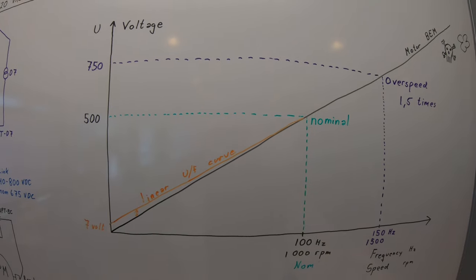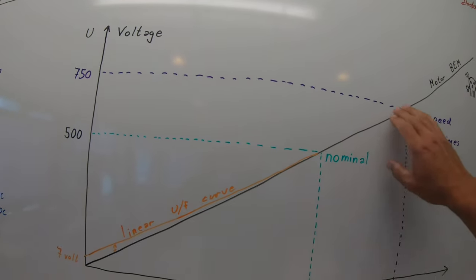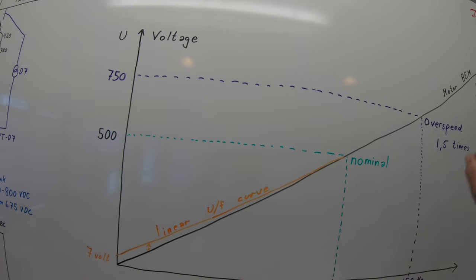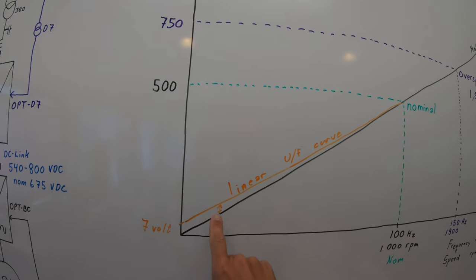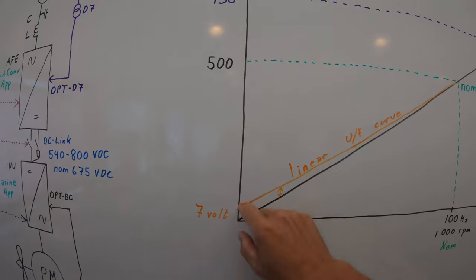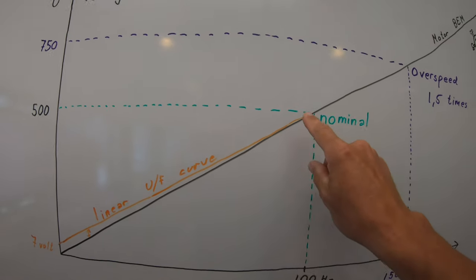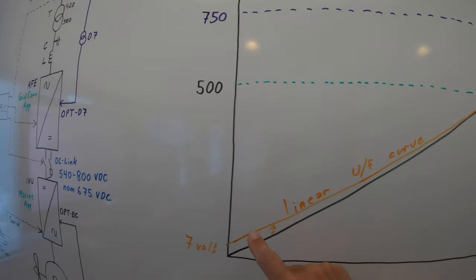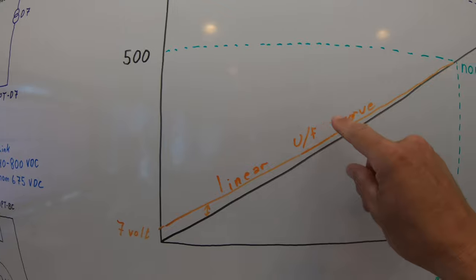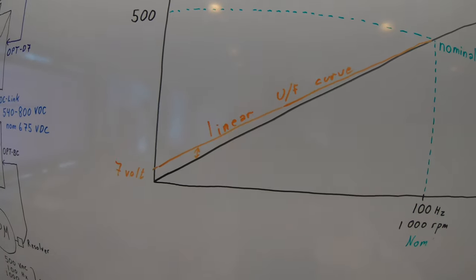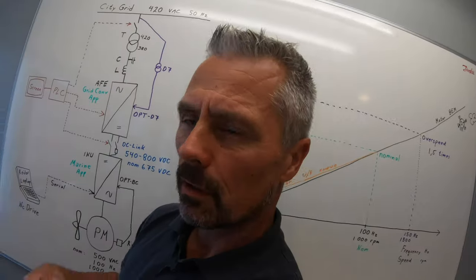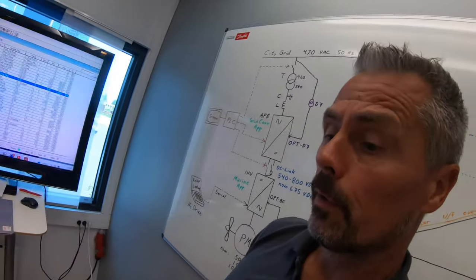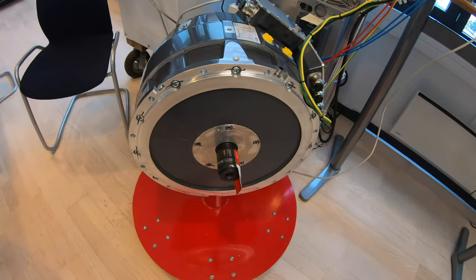How does this look on our back EMF curve? The motor itself, if you spin it, it will produce this back EMF voltage. And this orange color is now our linear UF curve. Here we start at 7 volts which will produce some kind of current, and then up to nominal. It will probably stop here, so actually the current will be a little bit up and then go down. In linear, this is just a rotation check, just to make sure that the motor runs in correct direction and everything is smooth and nice on the mechanical side.